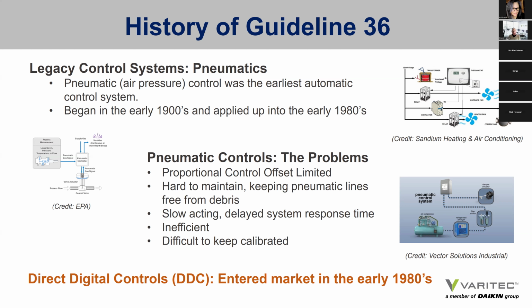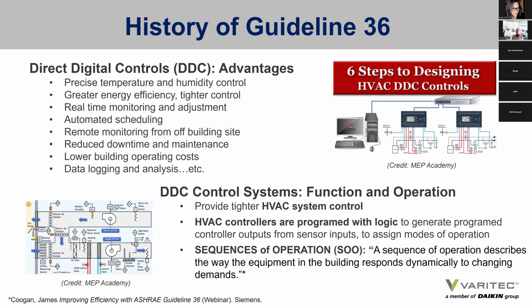Direct digital controls, or DDC controls, entered the market in the 1980s. Direct digital control advantages were these. They offered precise temperature and humidity control and monitoring, greater energy efficiency because they offered tighter control, real-time monitoring and adjustment, automated scheduling, remote monitoring from off-building site, reduced downtime and maintenance, etc., etc. So DDC control systems function and operation provided tighter HVAC control for more efficient operation. Well, what defines the actual operation of a DDC control system? Sequences of operation. A sequence of operation describes the way the equipment in the building responds dynamically to changing demands.